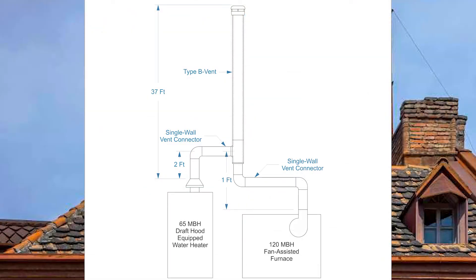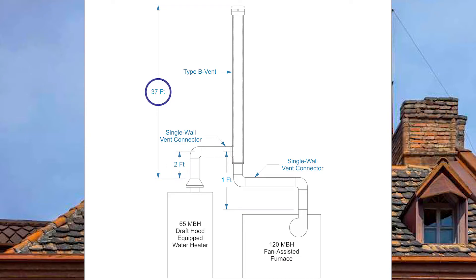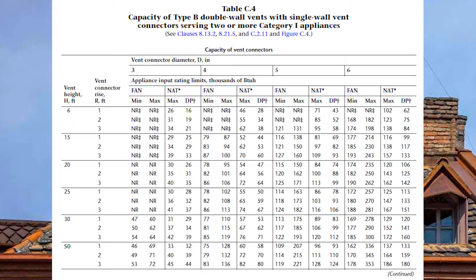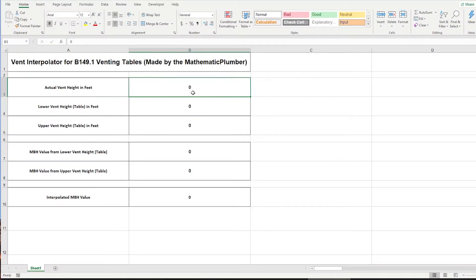Let's get more practice with the calculator using a second example. I have a 120 MBH fan-assisted furnace with a 1-foot vent connector rise, and a 65 MBH draft-hood-equipped water heater with a 2-foot vent connector rise and a 37-foot vent. The vent connectors are single wall and the vent is double wall, so we should be using Table C4. In Table C4 there is no 37-foot vent height — there's a 30-foot and a 50-foot, so let's enter those into the calculator.